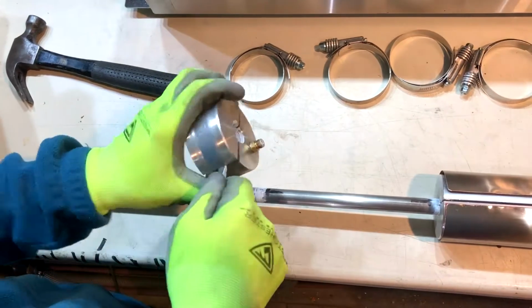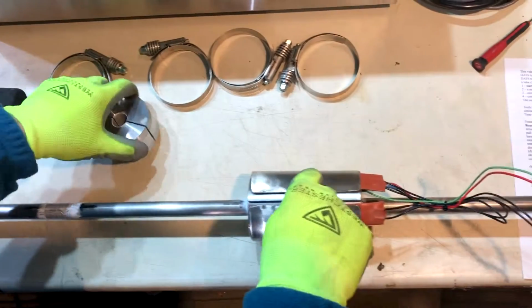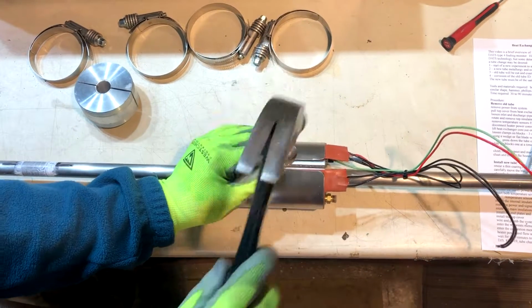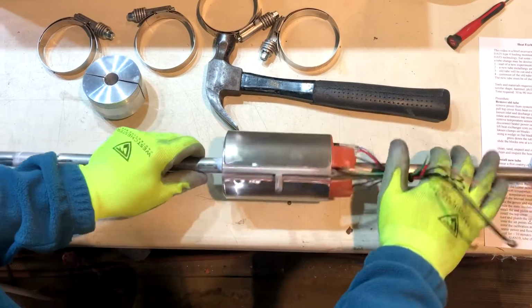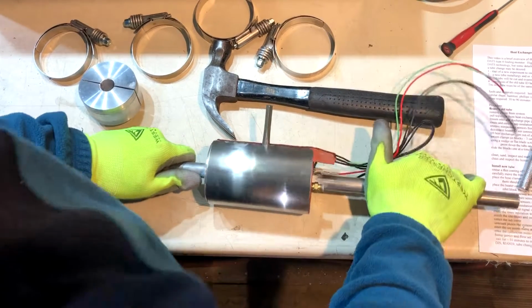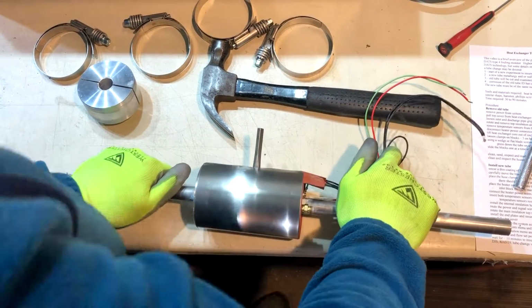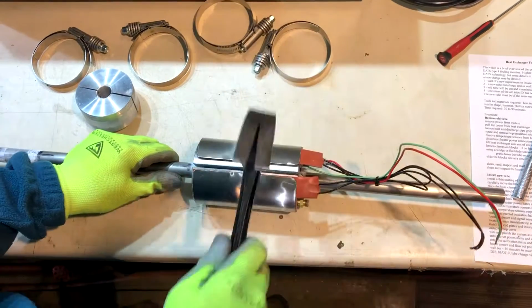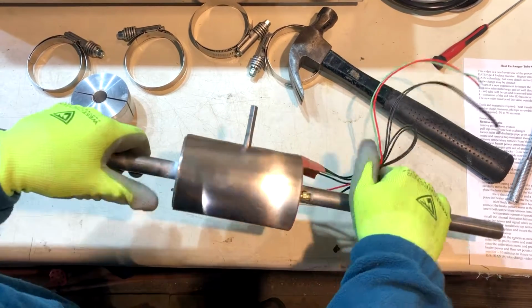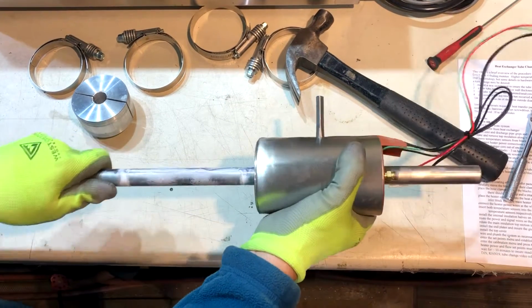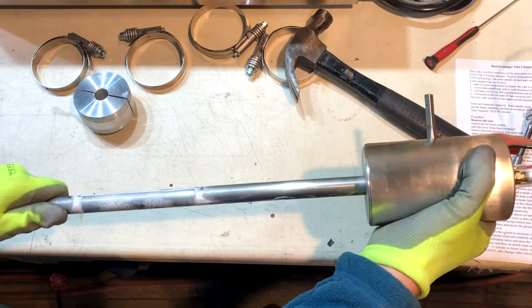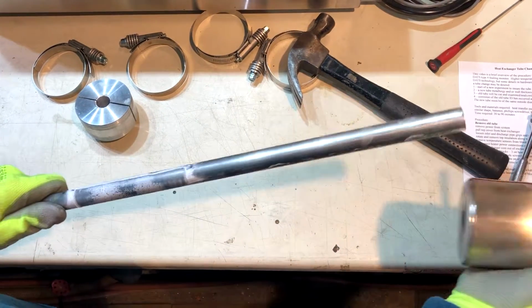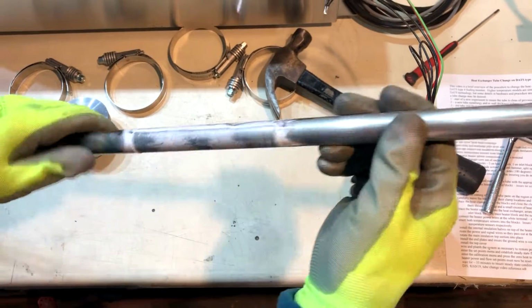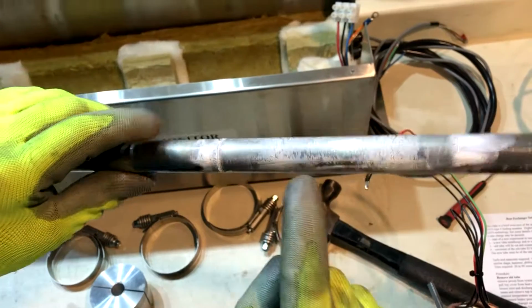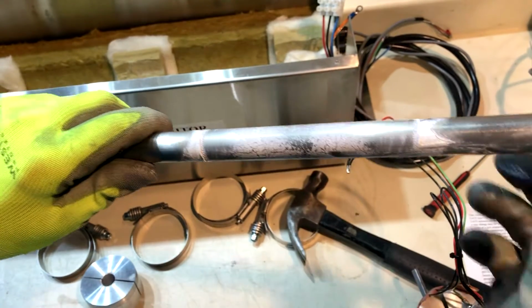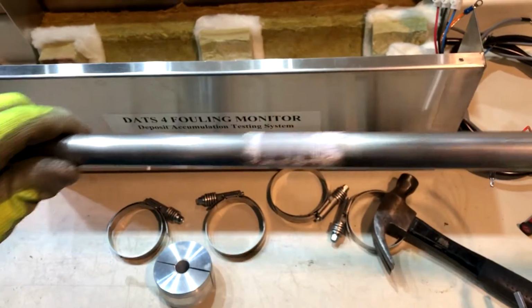the inlet block. Similarly, we can do the same with the main heater block. And let's just give that a try right now. Again, push both directions. I've got a little grit on this table here. Oh, she's on there pretty good. There we go. And sometimes a little more persuasion is required. Gently remove the tube from the block and ensure that you have no sharp edges on the end of the tube, which will damage the soft aluminum heater block. This is what the heat transfer paste should appear like beneath the heater block, showing that you've had a good clamp and intimate thermal connection with both those components.